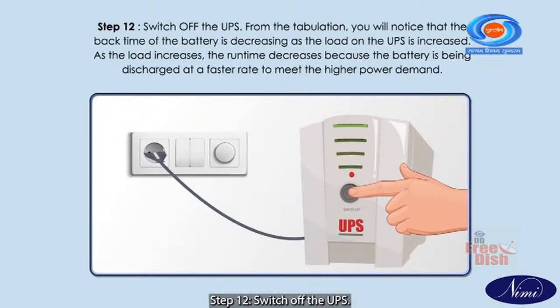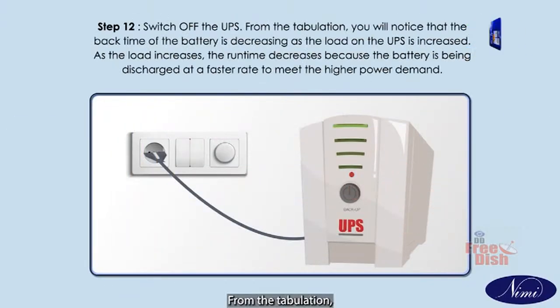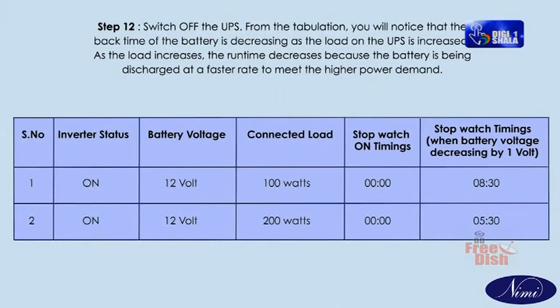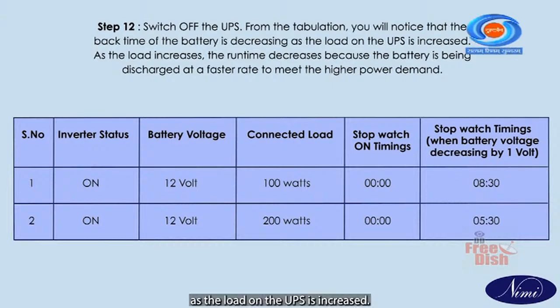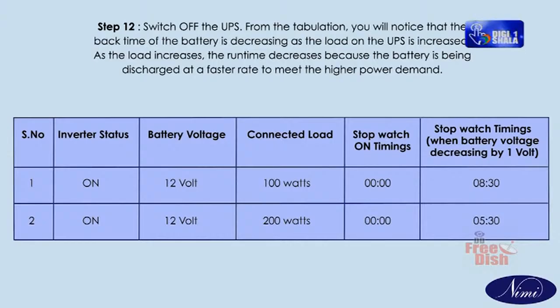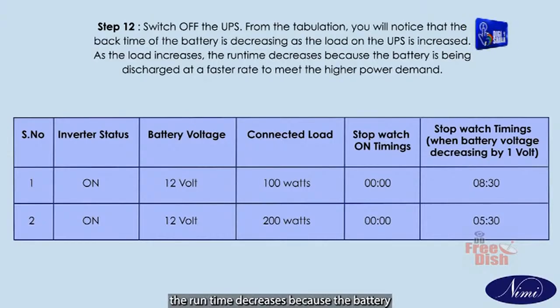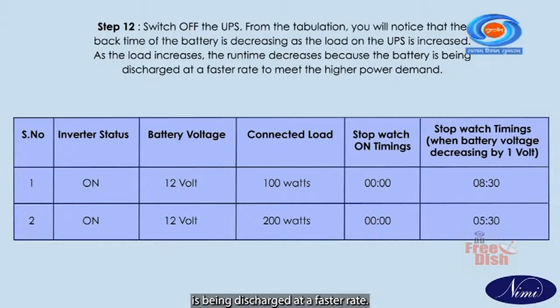Step 12. Switch off the UPS. From the tabulation, you will notice that the backup time of the battery is decreasing as the load on the UPS is increased. As the load increases, the runtime decreases because the battery is being discharged at a faster rate to meet the higher power demand.